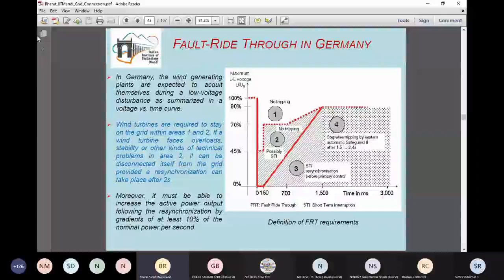Yes. So this is the fault ride through capability curve from the German grid code, so let's discuss this one. This red thick line is the fault ride through curve. The x-axis is time in milliseconds, going from 0 to 150, 700, and then 3000 milliseconds. The y-axis is the voltage at the point where the wind farm or wind turbine is connected. So this curve says that when the voltage is reduced to 0, even during 0 to 150 milliseconds, tripping of the wind turbine is not allowed.